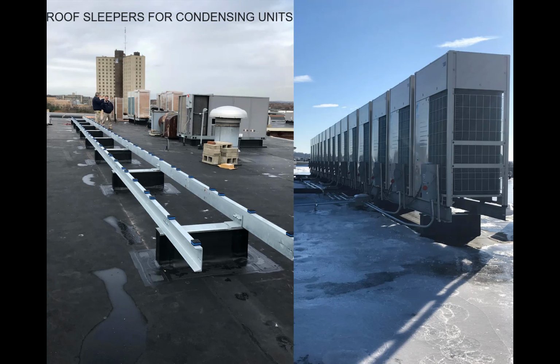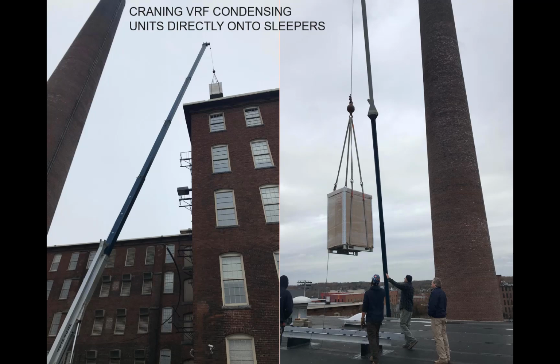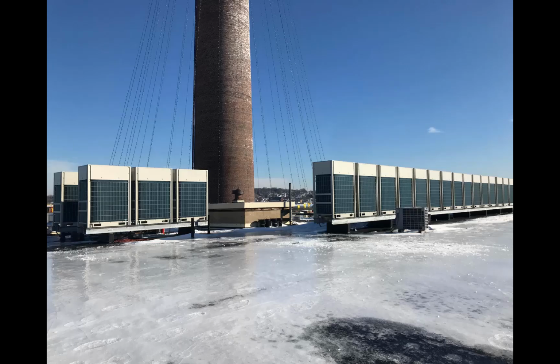Here's on the roof. You can use snow stands, like Greg mentioned. For a lot of units, it's often more cost-effective to put these sleepers. And also, usually vibration is not an issue because the machines are internally isolated. However, we're right above an old structure, right above the tenant space. So we actually put springs inside of these sleepers for additional isolation of sound and vibration. There's a picture of us lifting units. I always love to do those, and that's the final picture. So I'll leave it there just because we're already way over time.